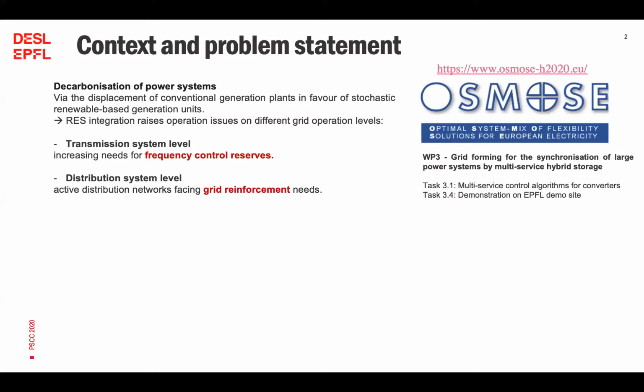For the transmission level, the transmission system operator, or TSO, has to maintain the balance always between generation and consumption. So this increasing fluctuation nature of the generation poses challenges in terms of speed and amount of primary reserve for the control. Regarding distribution grids, distribution system operators are seeing their distribution grids affected by local technical issues such as component congestion or large voltage deviations.